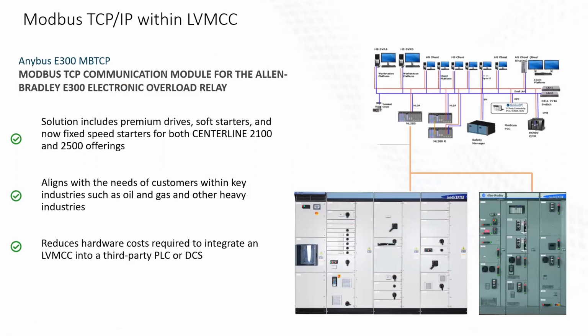We now have a Modbus TCP module. It's made by one of our Encompass partners, Anybus. It's the E300 MBTCP. This comes into play when maybe Rockwell's not the control system being utilized, but they still want to use one of our MCCs. So if we have an older DCS that might be using Modbus TCP, this gives us the ability to communicate to it. We can serve up or have up to 64 nodes on the system. And unlike our E300s, this is programmed through a web browser. It doesn't have quite as tight integration as we have with our standard E300 comms modules, but we are able to get all that data through the Modbus registers. All right, next one.